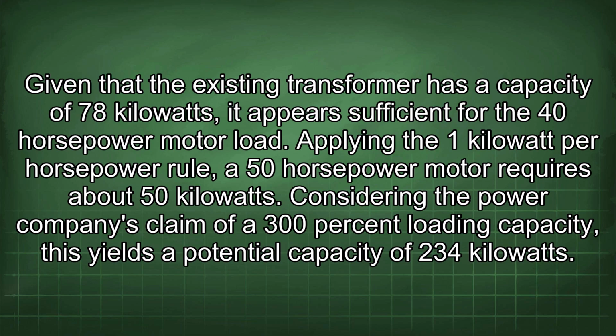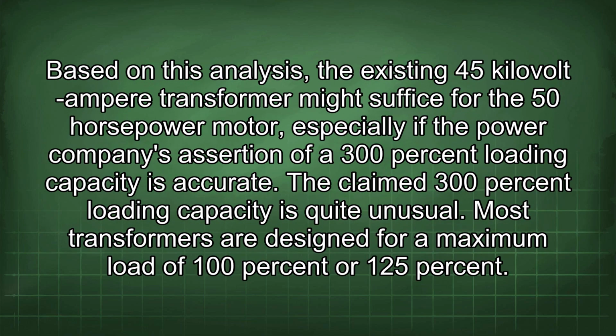Applying the 1 kilowatt per horsepower rule, a 50 horsepower motor requires about 50 kilowatts. Considering the power company's claim of a 300% loading capacity, this yields a potential capacity of 234 kilowatts. Based on this analysis, the existing 45 kilovolt ampere transformer might suffice for the 50 horsepower motor, especially if the power company's assertion of a 300% loading capacity is accurate.